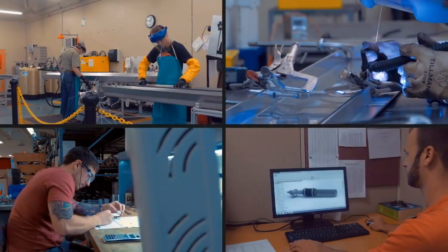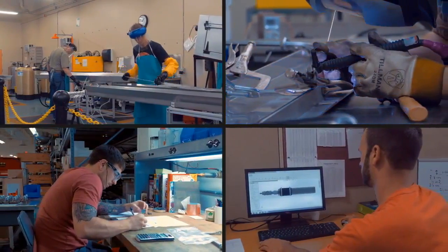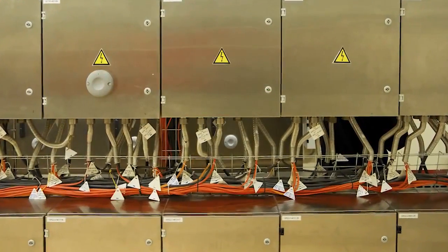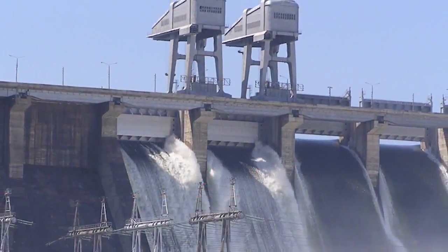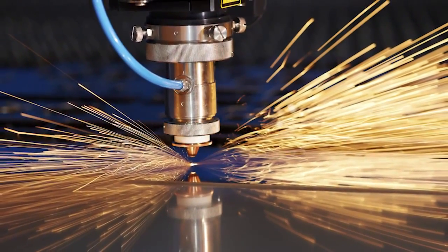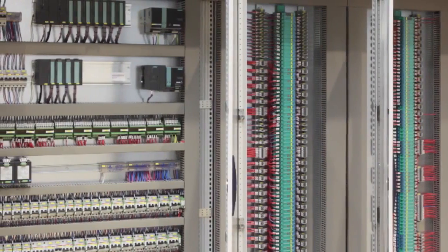At Advanced Cooling Technologies, we've been working on pumped two-phase cooling systems for more than 10 years. We develop standalone, completely self-contained cooling systems for several high-power electronic applications. One of the common requirements of these applications is that the cooling system must provide coolant from a single source to several evaporators simultaneously, with each having a different heat load.